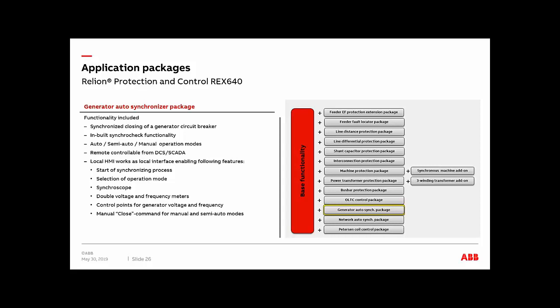And if you do have everything manual, you can use your local HMI as your interface for starting the synchronizing process. You can select the operation mode as well. There is something very interesting, which is that the relay will show you a synchroscope in your HMI, and you can visualize the synchronization process in real time there through the synchroscope. There are double voltage and frequency meters that will show you the parameters of each side of the generator and bus that you're trying to synchronize.